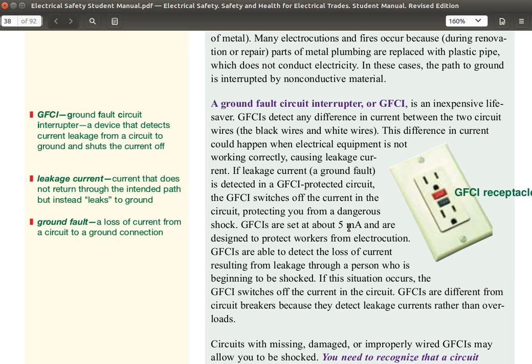But if 95 milliamperes are going back, it means 5 milliamperes are leaking through the person's body and the GFCI trips. If less, for example, 94 milliamperes are going back to the plug, then 6 milliamperes are shocking someone, going through their body to the ground. And the GFCI will detect that and trip. And they can trip within 1/40th of a second.